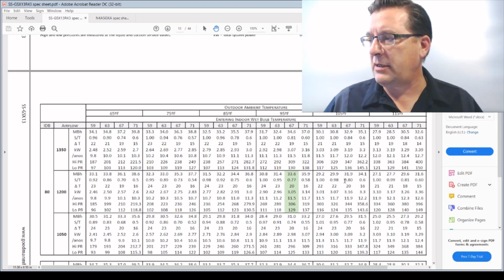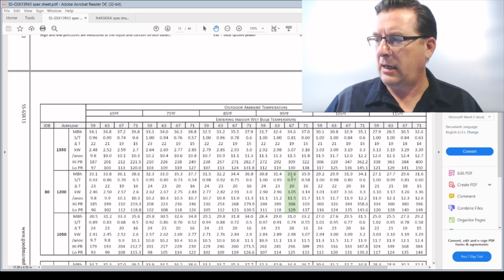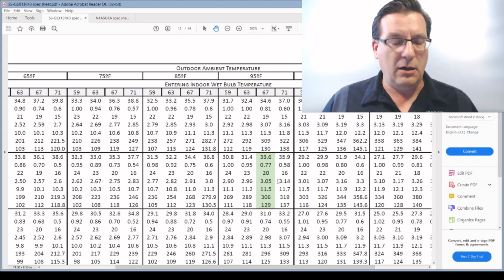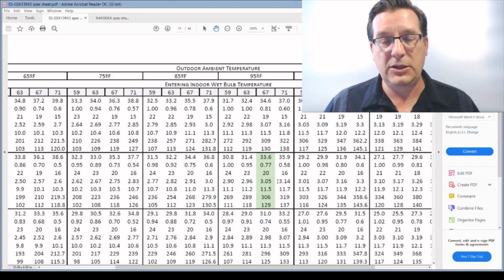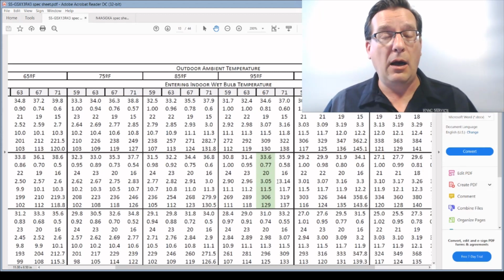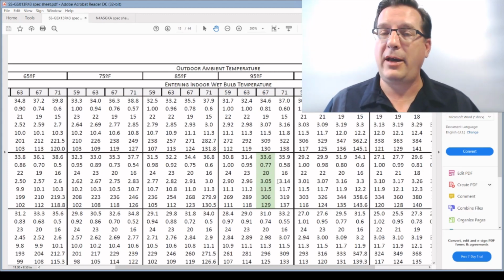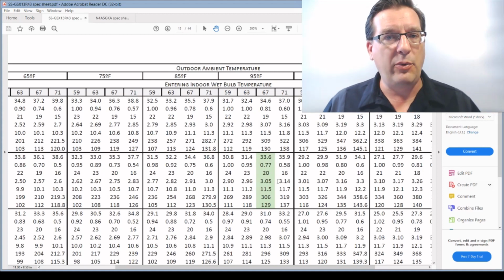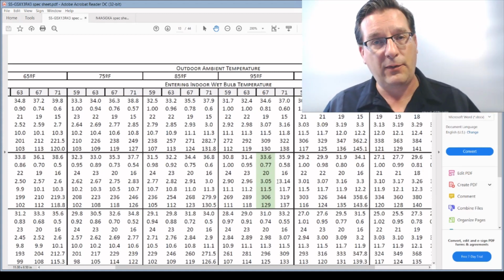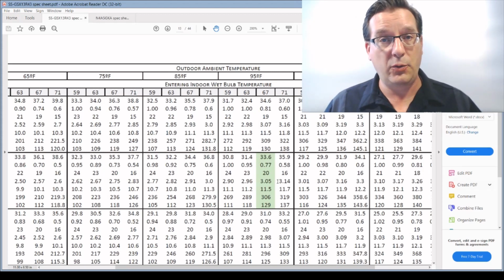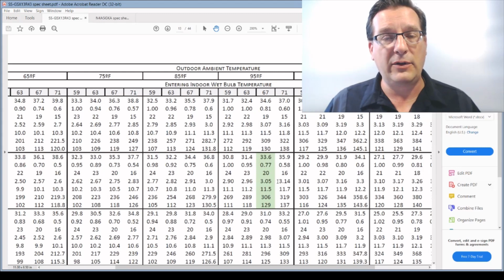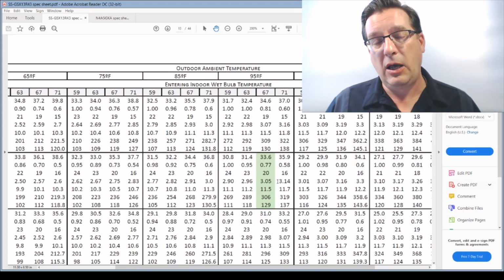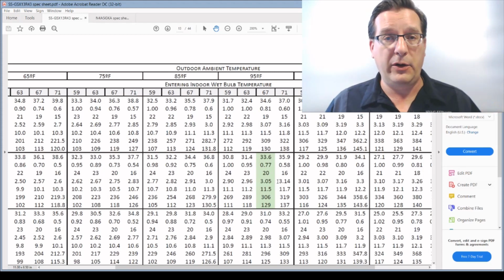You'll notice that there is a specific column or series of numbers that is highlighted in green. These are the AHRI design conditions, also just simply known as design conditions. When the air conditioning system is rated, all air conditioners are rated under the same type of operating conditions. Why? Operating conditions can do and will affect air conditioner performance. It's very, very important that if you're going to analyze your air conditioning performance, you have to know the conditions under which it's performing. So we have to have that level of understanding. This chart will give us some idea of the different levels of performance we can expect from this unit when we have a variety of different operating conditions.